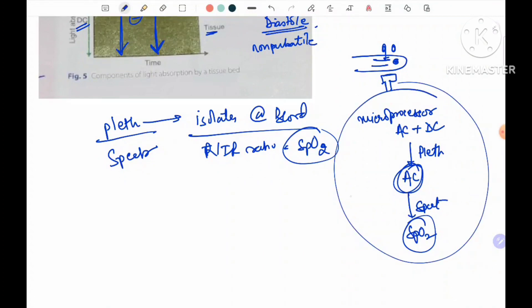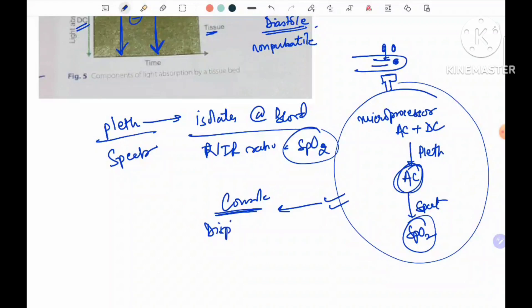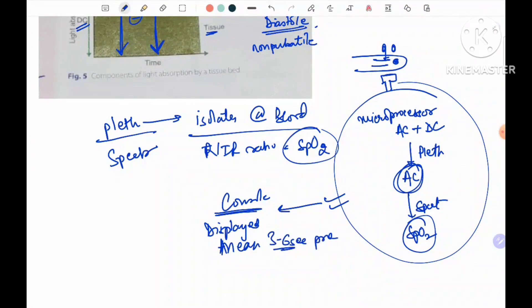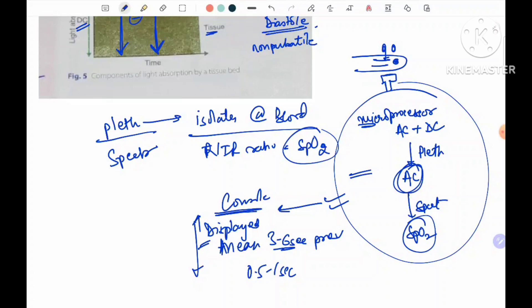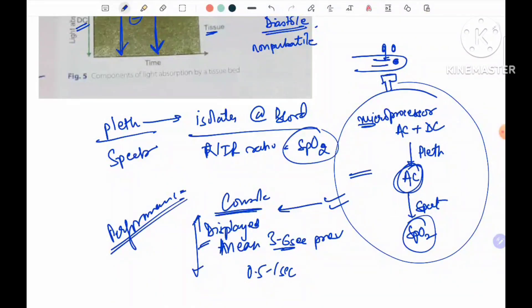Once this analysis happens, it is sent to the console for display. The value displayed is usually the average or mean of the previous three to six seconds of measurements, and it is updated every 0.5 to 1 second. The speed of the processor - how fast it can analyze and display the data - is what the performance of the device depends on, along with the reliability of the microprocessor and its algorithms.